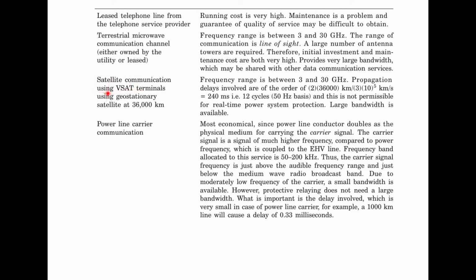Now, satellite communication via VSAT terminals using a geostationary satellite at 36,000 kilometers. The frequency range is between 3 and 30 gigahertz. Propagation delays involved are of the order of 2 into 36,000 kilometers, that is 240 milliseconds, that is 12 cycles, and this is not permissible for real-time power system protection. Large bandwidth is available in that case.